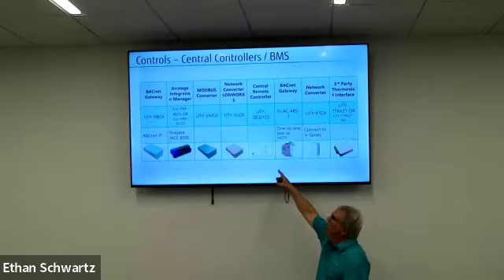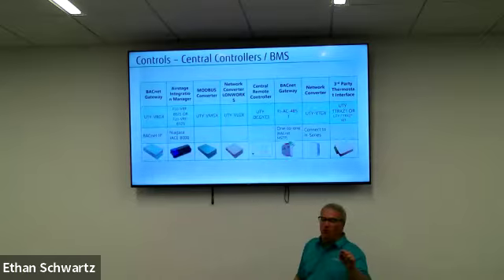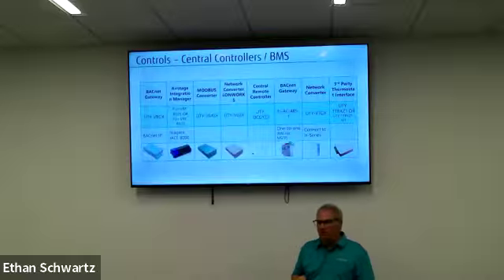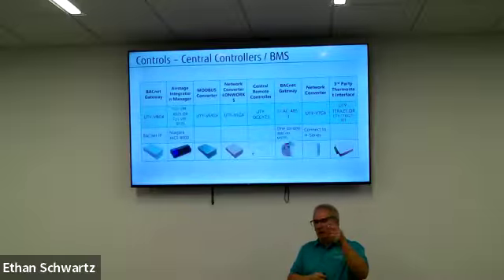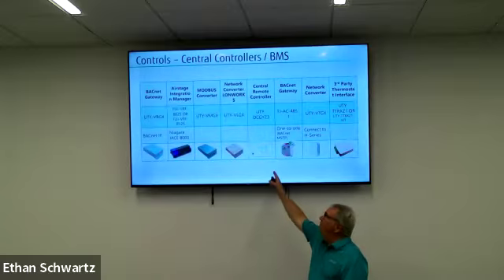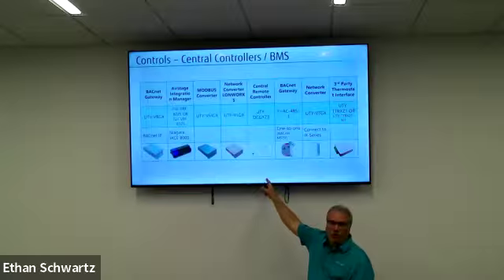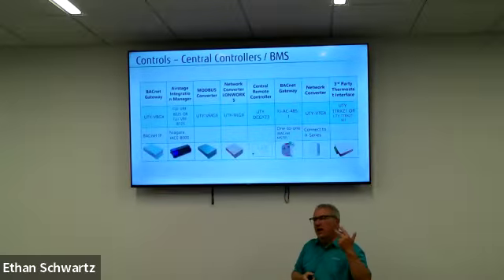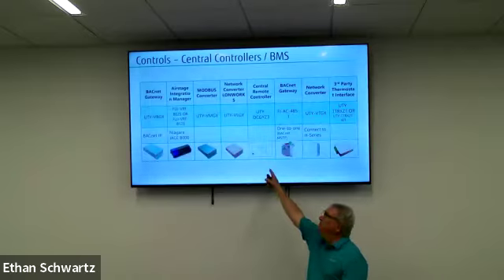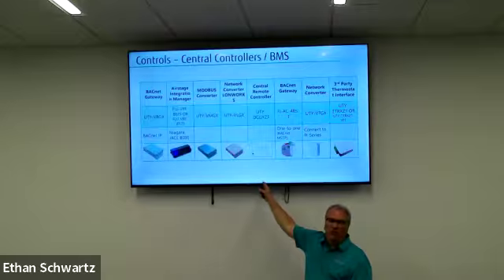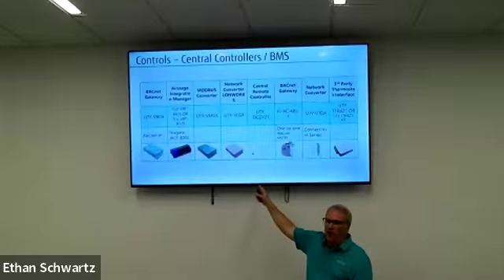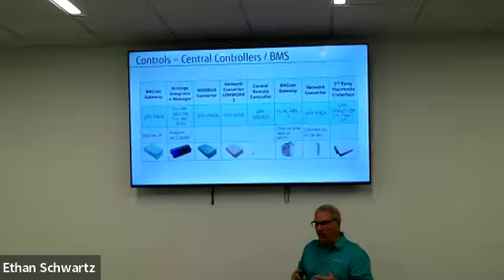But this controller, up to 100 indoor units, has this little tab right there. If you press that, and then you press the maintenance screen, that will pop up and one of the choices will be display sensor values. Then you press that, and it'll ask, do you want to see outdoor unit or indoor unit? If you select outdoor units, every outdoor unit that's connected to that controller, their head pressure, suction pressure, compressor speed, compressor amperage, the current RPM of their outdoor fan motor, the positions of the EEVs, all of that stuff will be displayed right on that controller, right for the service personnel to read out before they ever do anything. And then they can write that down. It's just going to be real time.